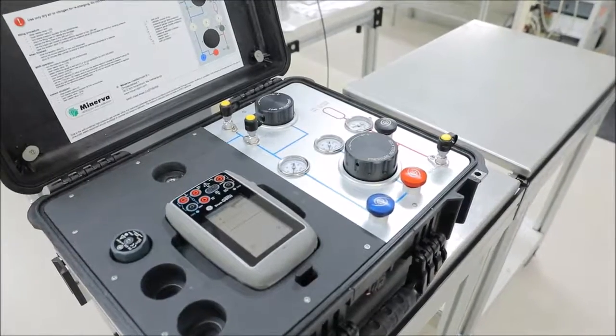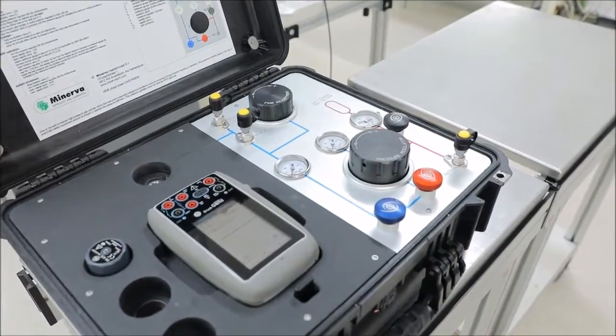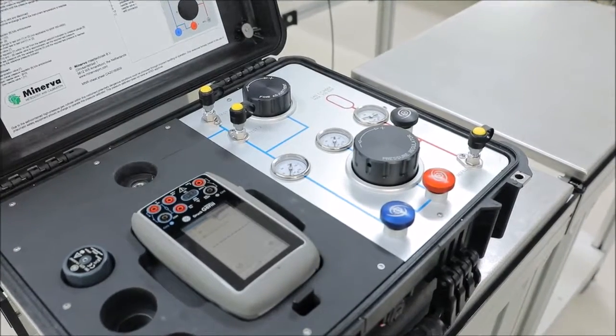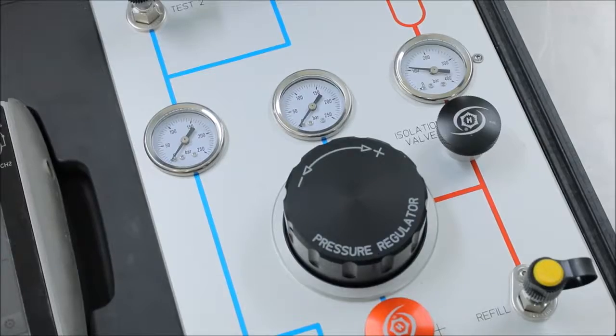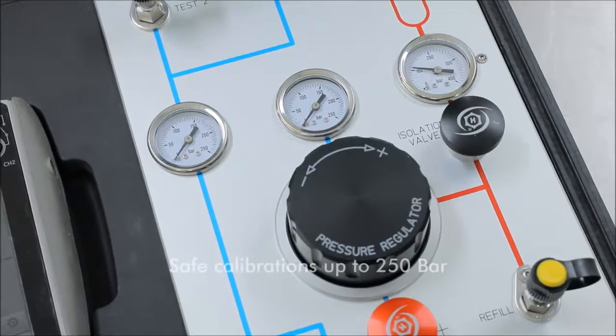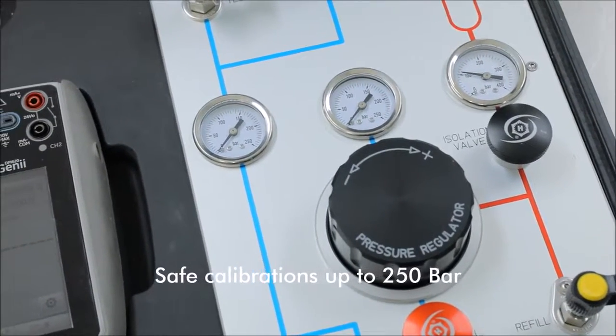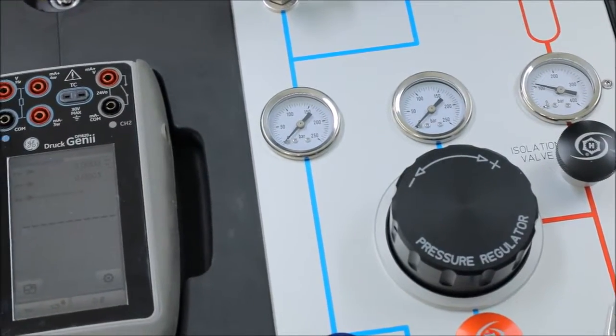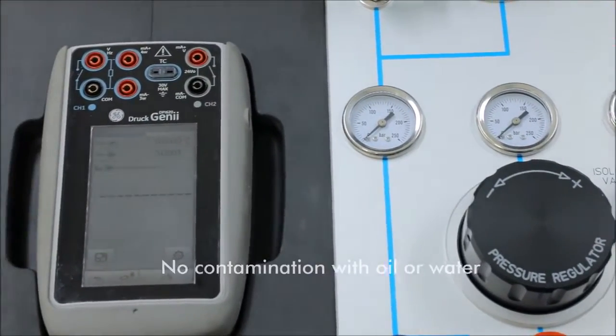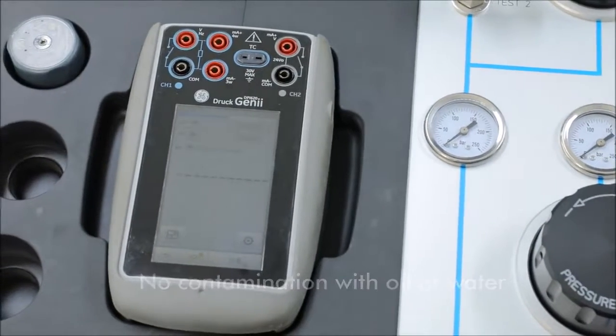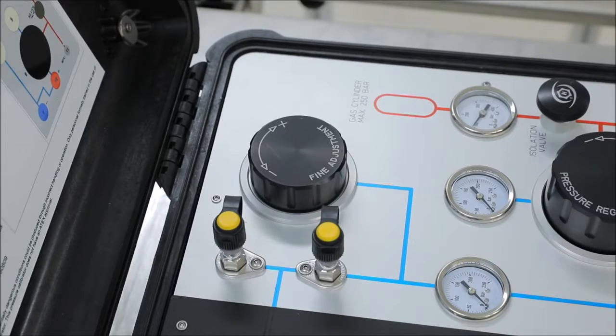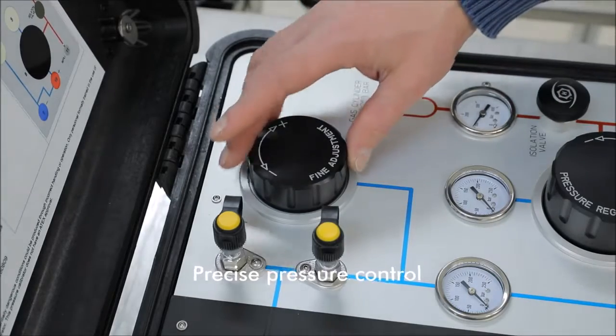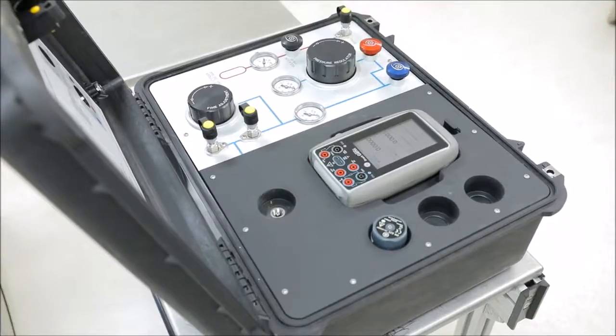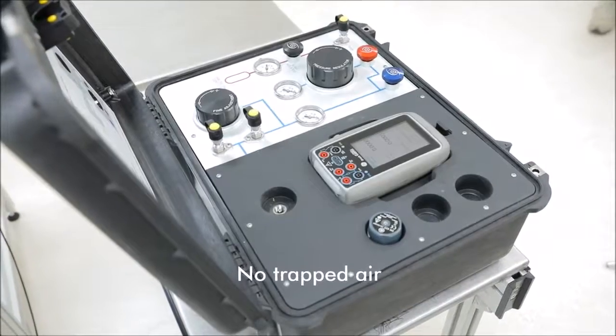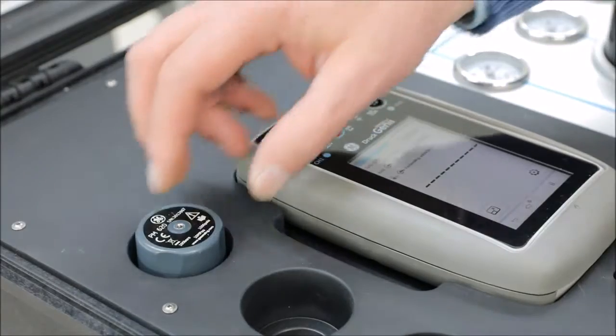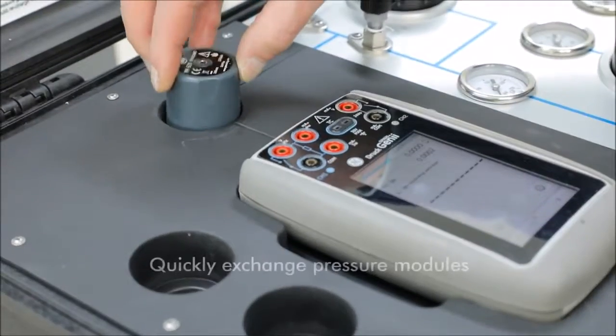This case offers improved efficiency to quickly and safely perform clean high pressure calibrations at your location. This case enables you to perform safe pneumatic calibrations up to a maximum pressure of 250 bars, not contaminate the device under test with oil or water, perform precise test pressure control using a pressure balanced volume adjuster, eliminate trouble with trapped air in a hydraulic system, exchange calibrator pressure modules quick and easy.